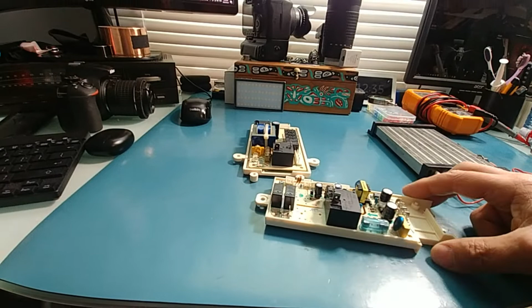The ones I've been using so far are basically for cars, but this one here is an indoor or window unit, rated for 250 volt at 30 amp. Like most relays, these have to actually be rated for 30 amp, because the compressor will pretty much burn them out if it stalls, so they've got to be rated for that constant.